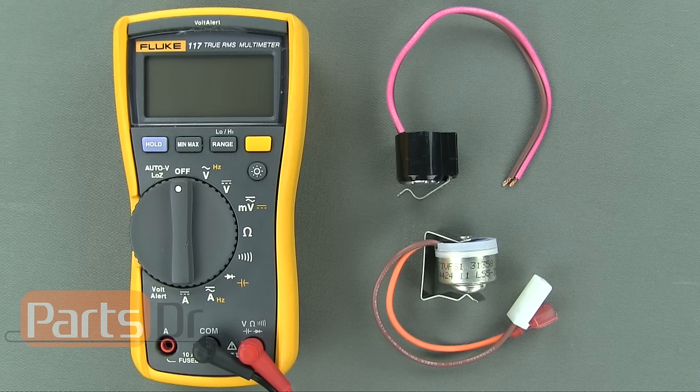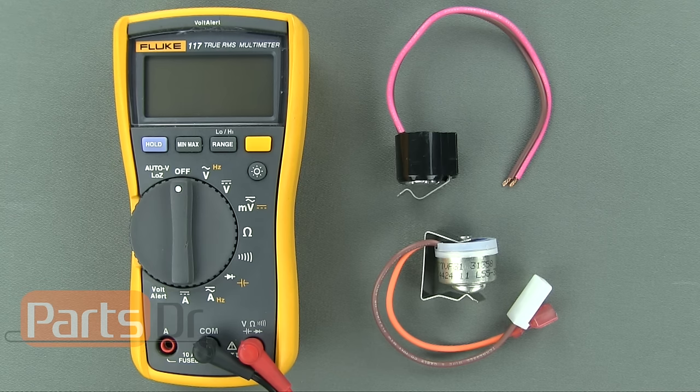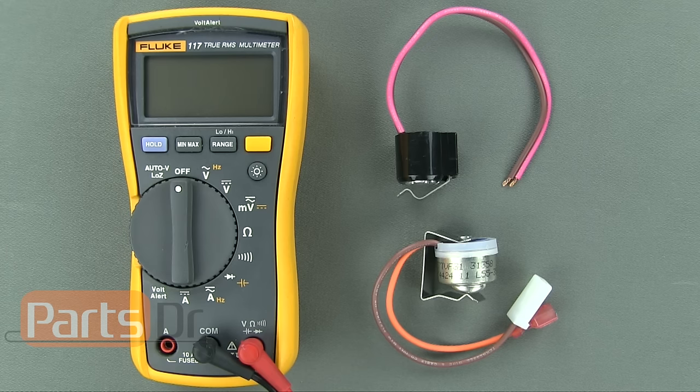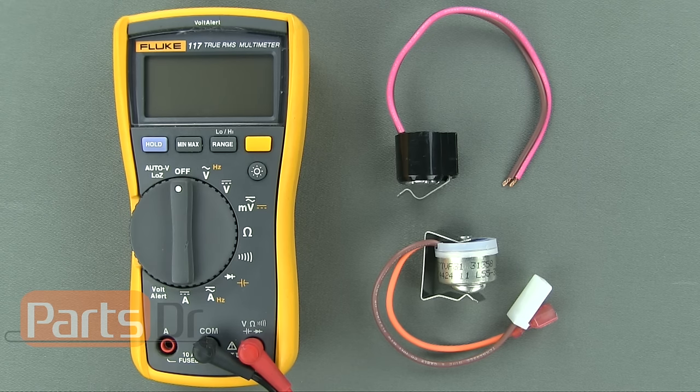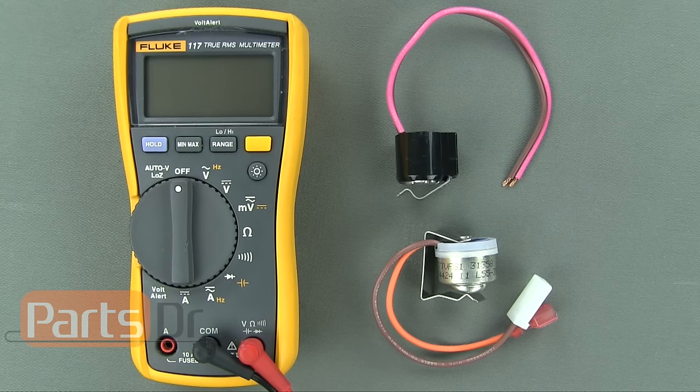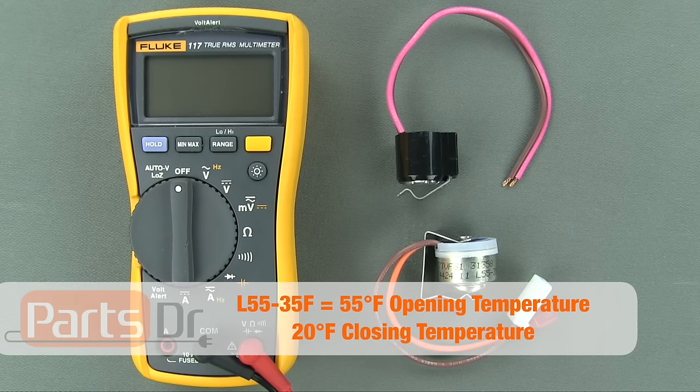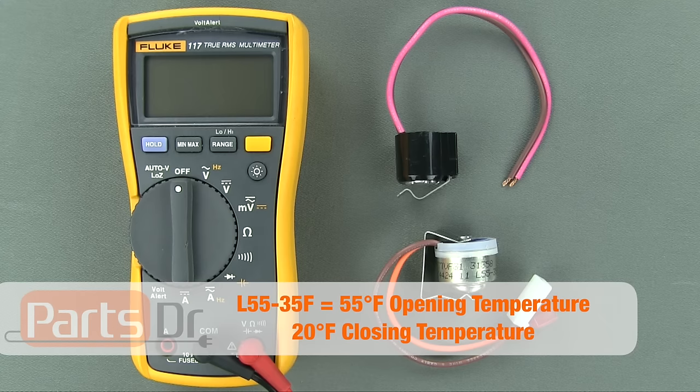The second number on the thermostat is often confused and thought of as the closing temperature. This is not correct. To get the closing temperature of the thermostat, you have to take the first number minus the second number. So in this case, we would take 55 minus 35 to get a closing temperature of 20 degrees Fahrenheit on this thermostat.